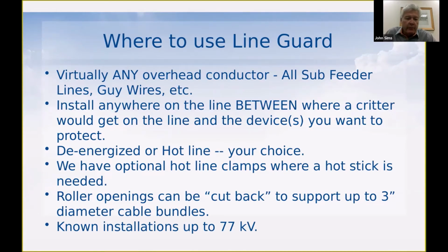Most of our customers use a de-energized install simply as a standard safety precaution. Some customers, though, don't have the redundancy in place, so they can't de-energize. A few still put them up hot, and that can be done as well with proper gloving. This is a snap system.